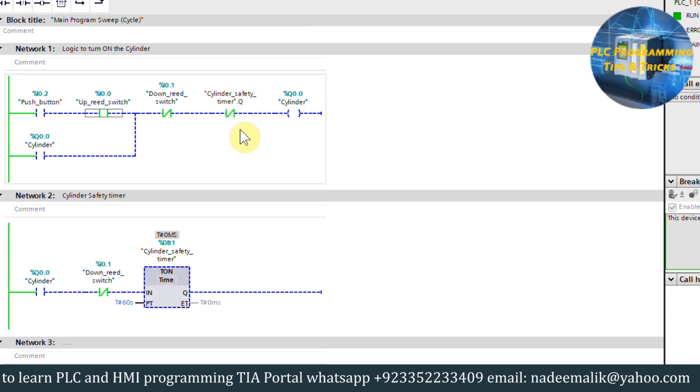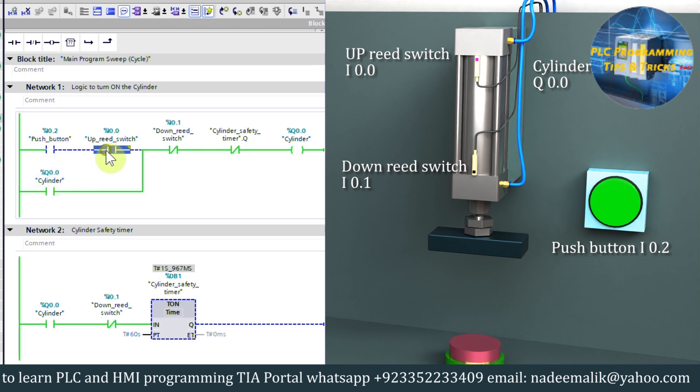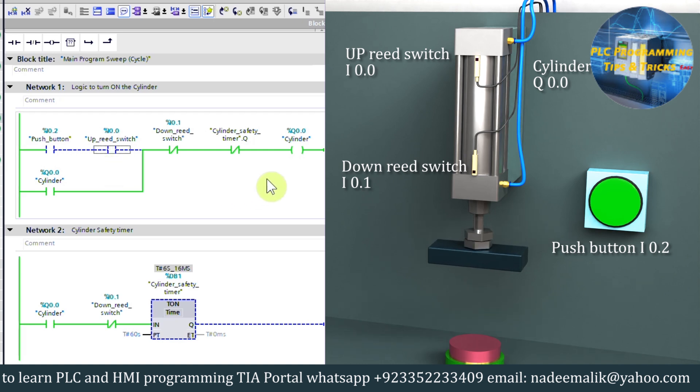Now let's try the program. As you can see, as soon as we press the push button I0.2, the cylinder output Q0.0 turns on and cylinder starts to move down. And this reed switch contact I0.0 opens as the cylinder piston moves away from it.